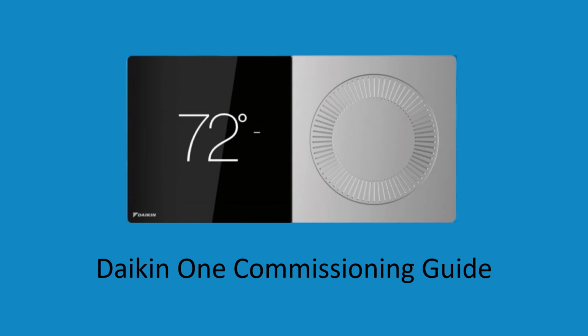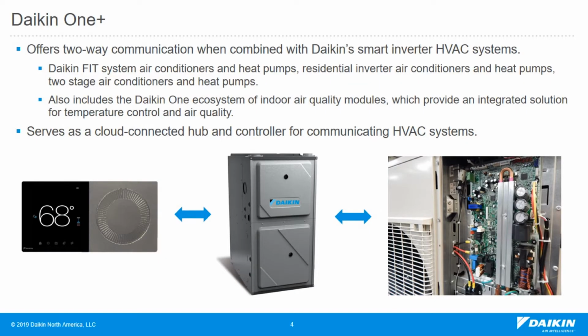Welcome to the Daikin One commissioning guide. Today we're going to do a quick review of the Daikin One thermostat and the commissioning process. The Daikin One thermostat offers two-way communication when combined with the smart inverter HVAC systems. Any communicating equipment can also use the Daikin One. It includes the two-speed outdoor equipment, the 16, the 17, the 18, and the 20.